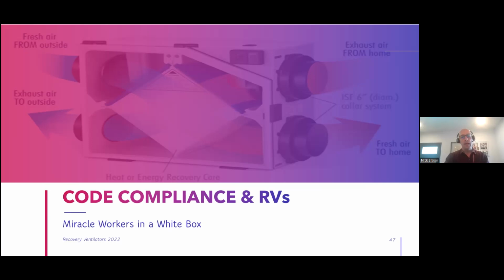Yeah, and Ari asks, what about the energy difference between balanced ventilation? Because I should have said that. A recovery ventilator is one enhanced form of balanced ventilation. Balanced ventilation means supply and exhaust within 10% of each other. And so you can do balanced ventilation without heat recovery by just pairing an exhaust and a supply fan, right? And so, yes, RVs will have slightly higher energy use than a balanced ventilation system because of the pressure drop. Typically, a balanced ventilation system is not going to have the same ductwork snaking throughout the house. But if it did, it'd be pretty darn similar. Little extra pressure drop in the heat exchanger core, though.